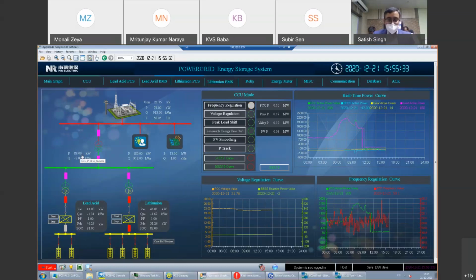If it is between the middle band, the battery will charge or discharge as per the grid event with a specified ramp rate that the user can define. And if the frequency deviation is very small, it will discharge at a different lower rate. We have also included an SOC management concept, so that if the battery is not doing anything, it maintains its state of charge to be ready for the next event. Let us go to the demo part.